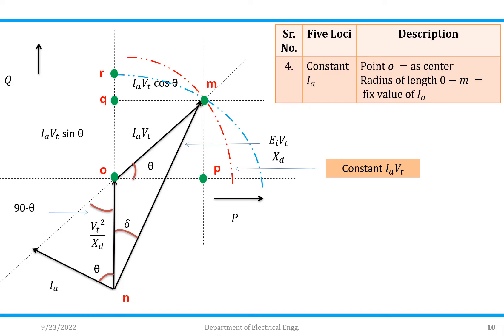The next point is constant IA. This constant IA curve is represented by the red color curve. Take O as center, and OM as the radius — because OM indicates IA·VT. Draw the curve with OM as radius, and whatever curve we get is nothing but the constant IA·VT curve. If your generator operates within this area and within this limit, the generator will be operated within a safe limit.